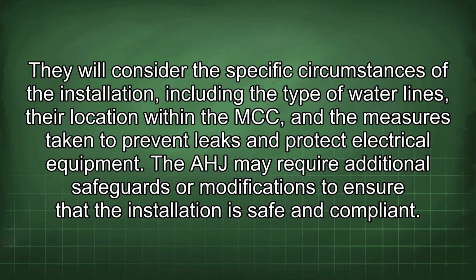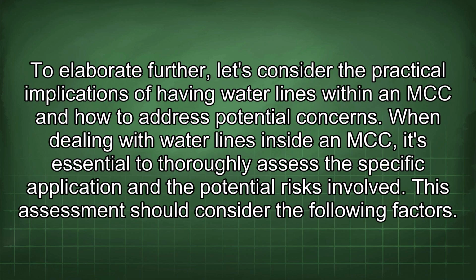They will consider the specific circumstances of the installation, including the type of water lines, their location within the MCC, and the measures taken to prevent leaks and protect electrical equipment. The AHJ may require additional safeguards or modifications to ensure that the installation is safe and compliant. To elaborate further, let's consider the practical implications of having water lines within an MCC and how to address potential concerns. When dealing with water lines inside an MCC, it's essential to thoroughly assess the specific application and the potential risks involved. This assessment should consider the following factors.